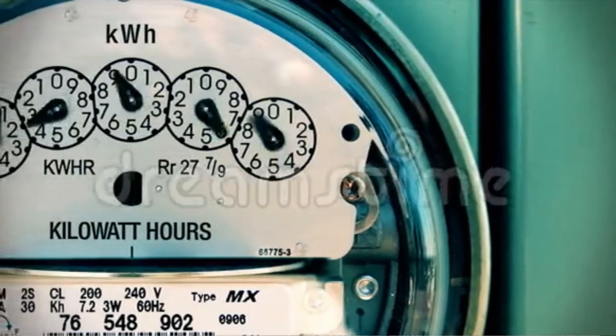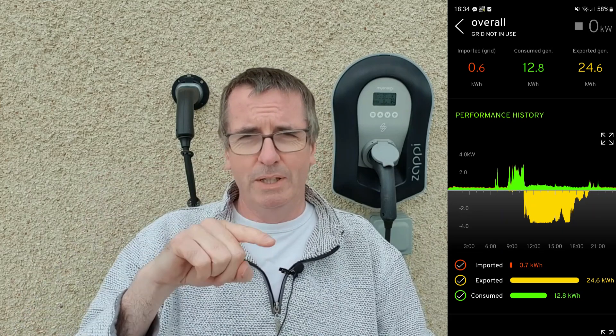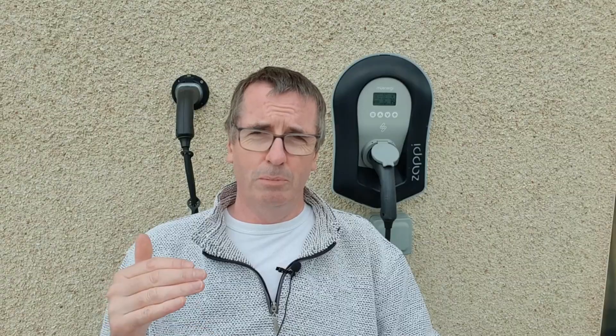Yellow is bad, as I've shown on this screenshot. It's not all bad because I am putting that excess electricity out onto the grid to my neighbours - it goes to my neighbours down the physical wires here in this little cul-de-sac and will power their fridges and electric kettles during the day. It is rather strange in 2022 that their meters will actually spin and they will be charged for the electricity they're getting from my house, because I'm not being paid for electricity I dump on the grid. I dump onto the grid at a maximum of around 3.8 kilowatts, which is why on the graph the hump is sharply chopped off at just below four kilowatts - that's the most I've set on my hybrid inverter to push out onto the grid.